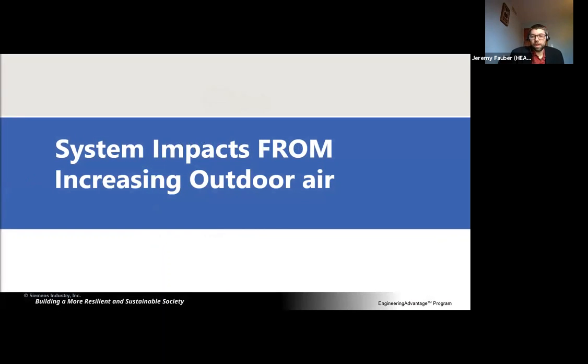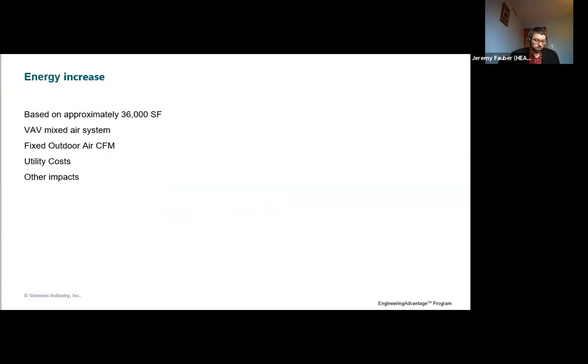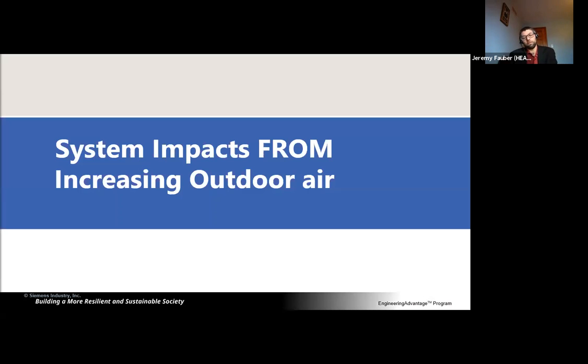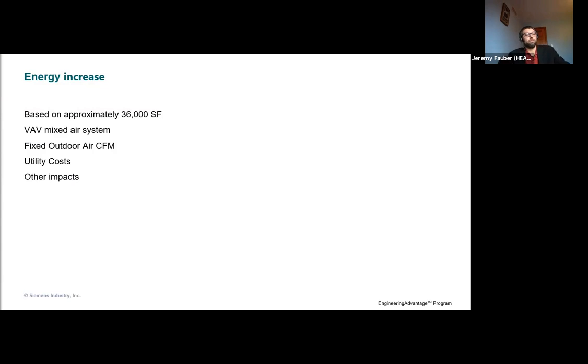All right, thank you very much, Matt and Tom. So I'm going to talk about system impacts for increasing that outdoor air. And the way I went about studying this is to start with an energy model. We took an energy model for a new office building, approximately 36,000 square feet. It's a VAV mixed air system, so it is recirculating air. It's not 100% outdoor air.